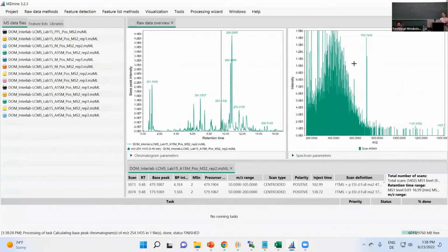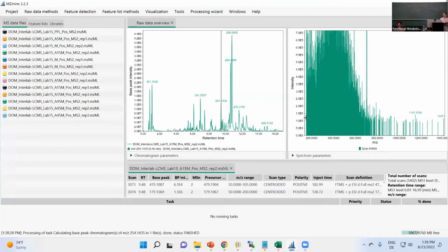So in the front, you have some signals that we want to process later on, and we also have a lot of signals at the same intensity. This is most likely due to instrumental noise. It can be from the detector, it can be neutral molecules hitting it if you have a TOF instrument or so, or electronic noise in the Orbitrap. So here, for example, for the MS1, we can see this noise at the level of 1E5, which is basically 100,000, whatever units the instrument gives.